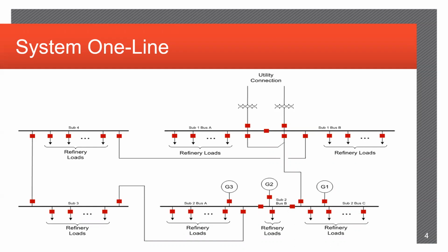Were there any specific challenges from conception all the way to commissioning? Good question. Probably the single biggest challenge was developing the logic itself. The second biggest challenge was testing that logic in an accurate and expedient manner, and that's where the automated testing really shone. Without that, testing this system would have been a nightmare.